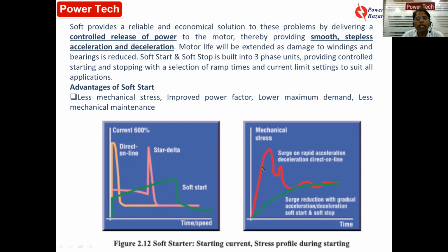So here mechanical stress is there, but here the mechanical stress is not there. It is a smooth ramping up or smooth acceleration. So the advantages of a soft starter are less mechanical stress, improved power factor, lower maximum demand, and less mechanical maintenance.